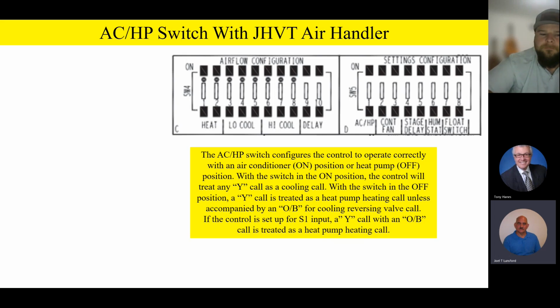Excuse me, a Y call is a cooling call, like a cooling unit, but it's going to be on the HMH7, it's going to be a cooling call. But if you put a BO with the HMH7, it becomes a heating call. So this is really important because the whole point of this lesson is that if you're set up with an S1 input, and that heat pump switch is in the heat pump position, it knows it's on an HMH7, and now it's going to treat that OB signal from the thermostat as a heating call on the HMH7.